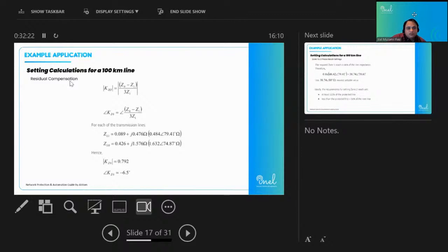There is another thing which is called the residual compensation, and this comes into action when there is an earth fault on the transmission lines. Because when the fault is on the phase conductors, their parameters are fixed. But when there is a ground included, like a one phase to ground fault or a two phase to ground fault, then we don't have the exact values in the calculation. But as per the calculations, we can add this residual compensation factor, which will give us the exact values.